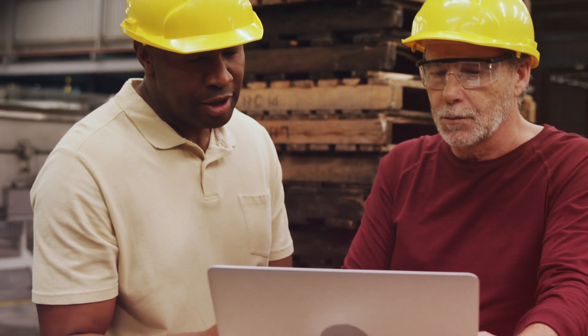The following day, Logan, who is also part of Rachel's Rockwell Automation support team, calls the shift control engineer. He notices a duplicate MAC ID error. With Logan's help, the control engineer is able to access the drive communications parameters and resolve the issue quickly. Logan also suggests some networking best practices to help avoid this type of issue in the future.